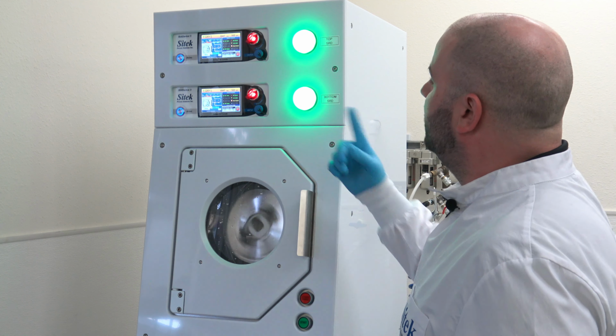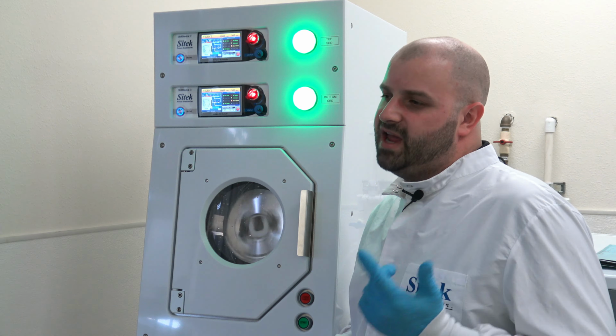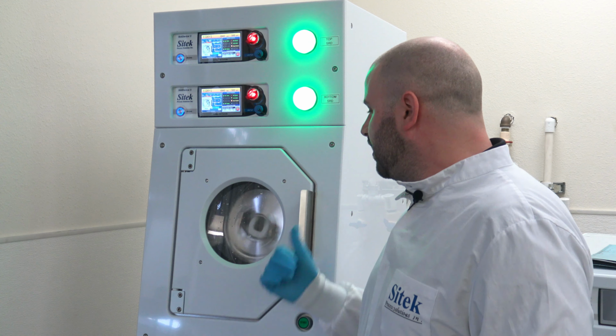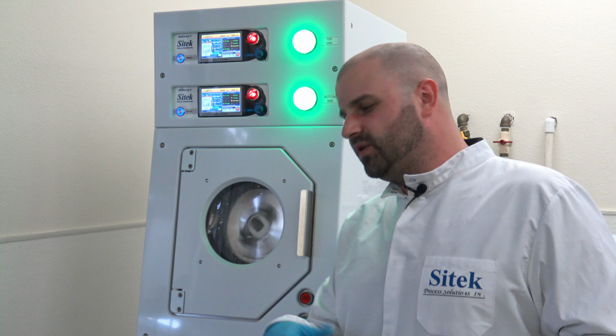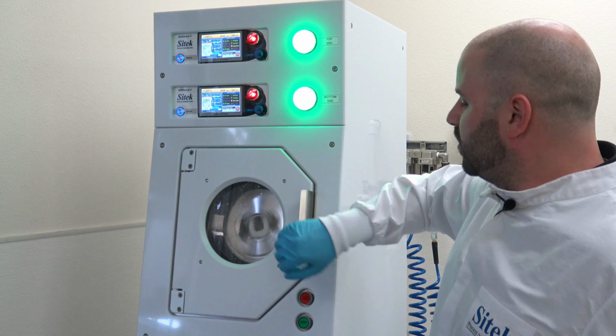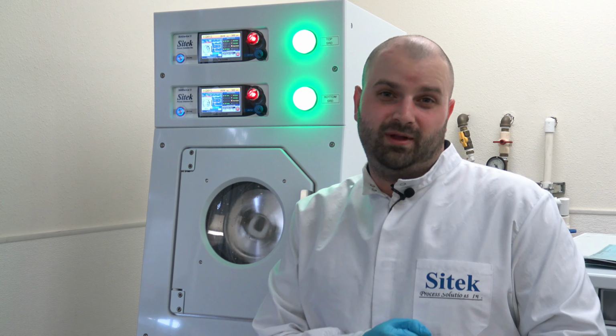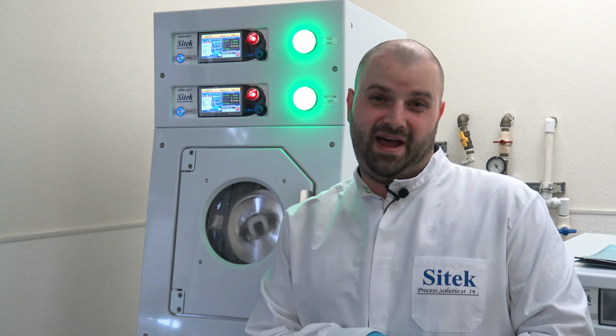45 seconds left. When the clock strikes 0, we don't want to open the door yet. We need to wait for the RSP to bring our rotor into the 12 o'clock position and for the door seals to release all air. If I force this door open, that causes problems, and you do not want problems in the fab.